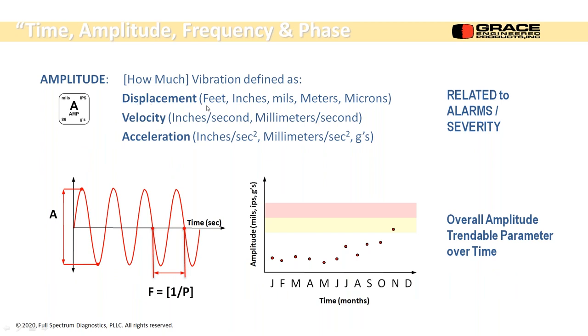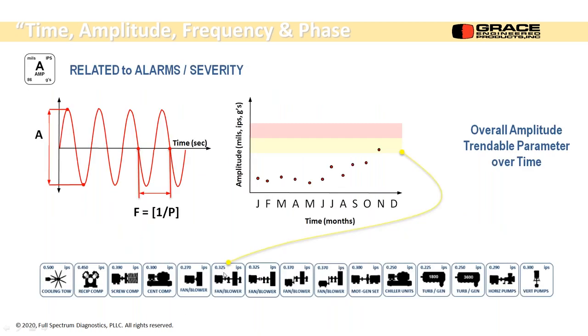What can these amplitudes be? They can be displacement in mils, typically, or microns. There's velocity in inches per second and acceleration in Gs. Those are the units that we prefer, right? Three different types of measurements. This is the one that's preferred, the velocity, and we'll tell you why in a few minutes here. All right, here's my alarm for my machine of interest, 0.325. I don't want to wait this long for this thing to creep up to failure. I want to see it right here, maybe, where something has changed and I don't know what that is. So we can pick up subtle changes, like I mentioned, with the online systems much faster.